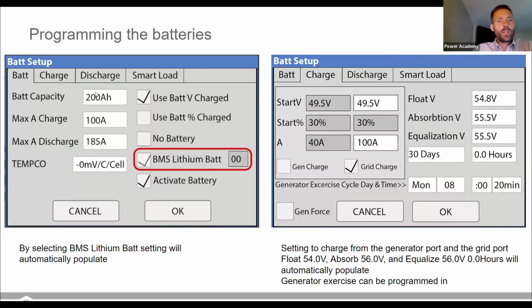Your overall battery capacity: if you're doing parallel inverters, you would want to put in the entire bank capacity. But the amount of charge and discharge, if you've got paralleled inverters, is per inverter. So keep that in mind. Total bank capacity goes in here; max charge and discharge you would want to put per inverter.